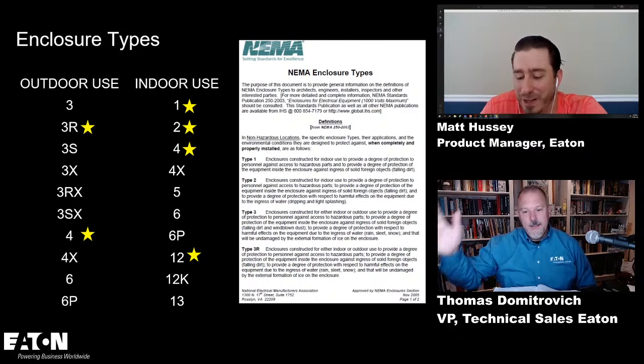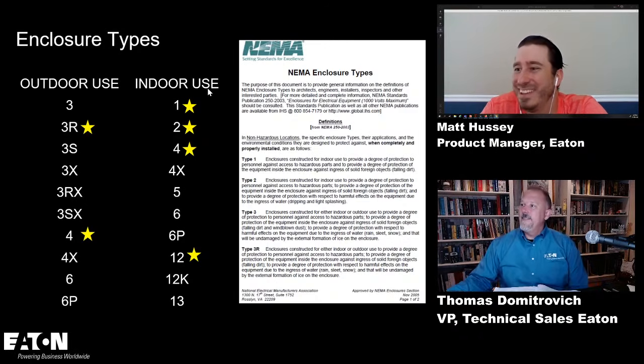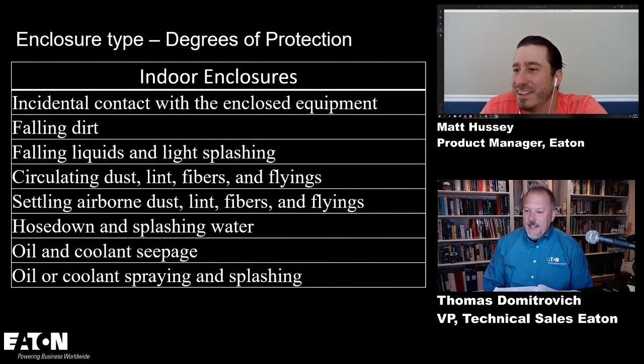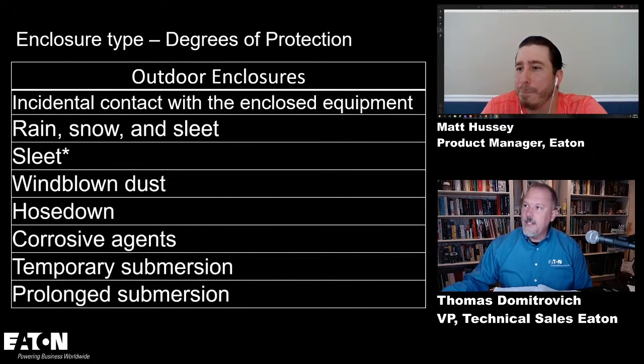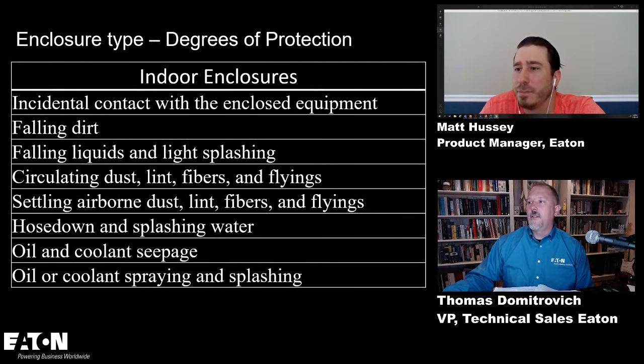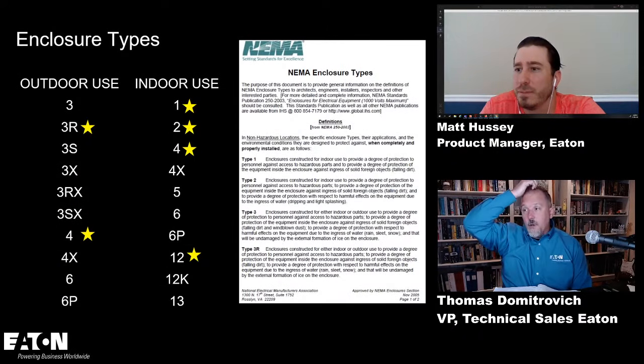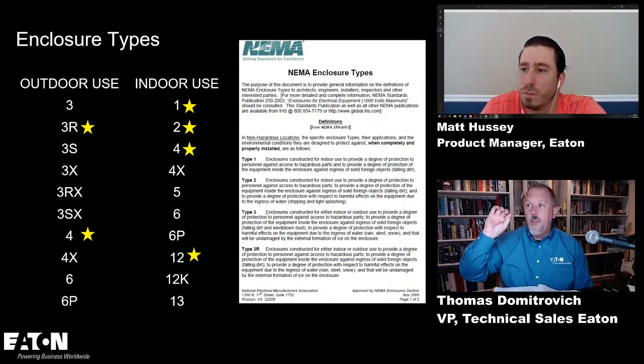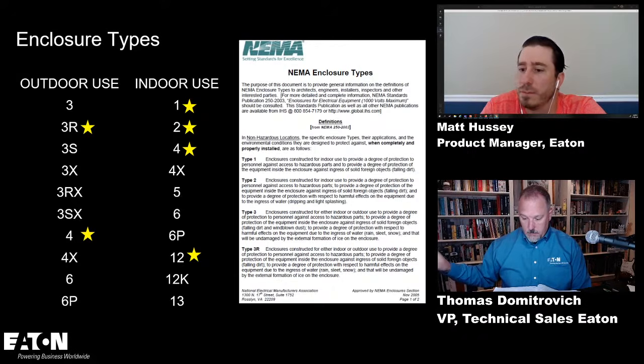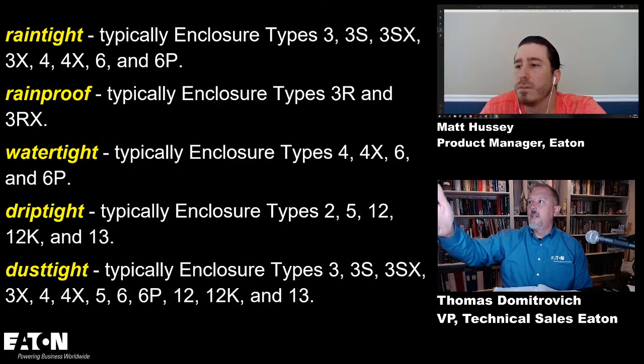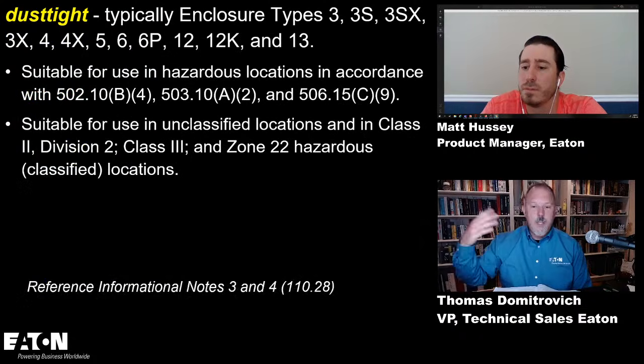Yep. And as we go along, we had a healthy discussion on that this morning. Yeah, we did. So there are the indoor enclosures and the outdoor enclosures, reference 110.28. And what you noted, going back to those stars again, is you can get a 1, 2, 4, 12, and a 3R in a motor control center. Yep. Okay. And then those enclosures will dictate where you can put it. All right. And let's keep going. I'm just looking at the informational notes. They tell you rain tight, rain proof, and what those are. So keep that in mind.